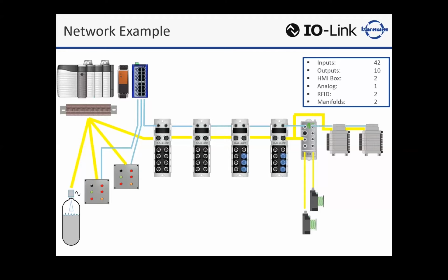Oh, that's excellent. So I think at this point, we'd probably be smart to do some cost comparisons between those two. Sure. So let's use your calculator. You've made this calculator here in Excel, and essentially we populated our IO. It gave us 42 inputs, 10 outputs. In this case, we put basically 8 in and 8 out for your two HMIs. Yeah, so 4 in and 4 out at each station. And then we're going to add that one analog. We put two manifolds out there with 8 valves each. Okay, and then we added the two RFIDs.